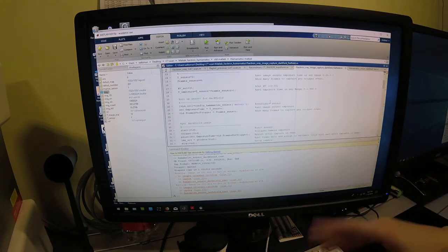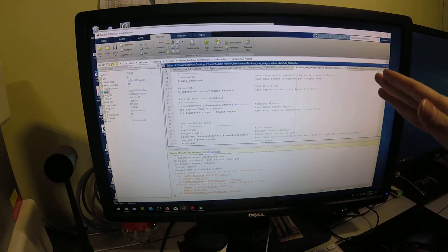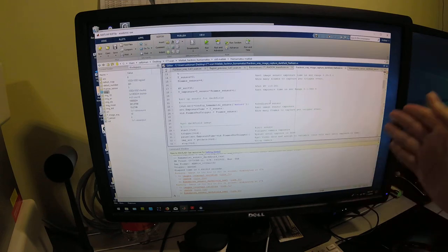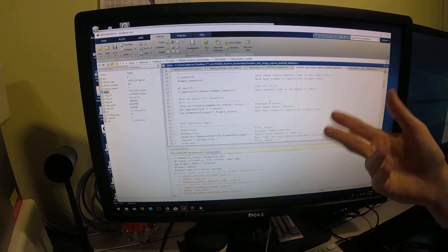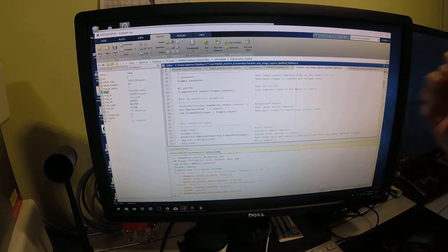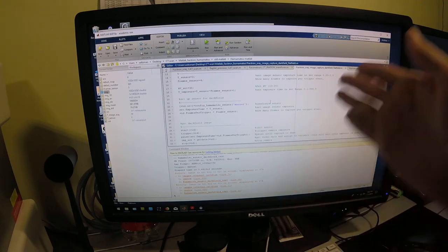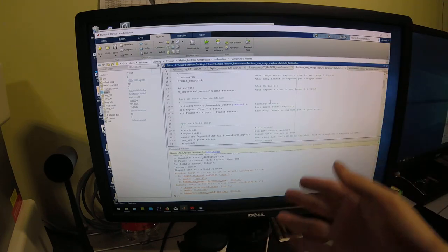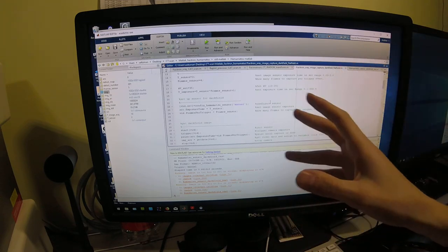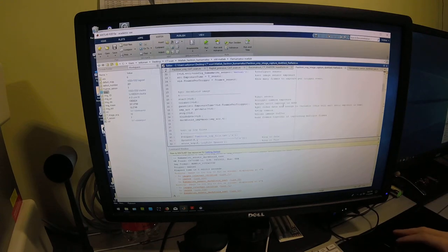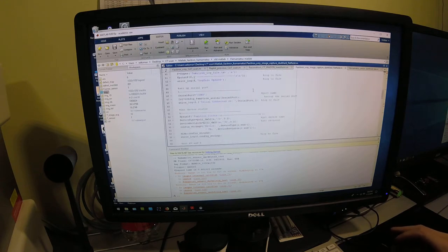In this case, there really isn't any expected heel effect, which would be inhomogeneities due to the angle at which the anode on the X-ray tube intersects the electron beam. The X-ray bremsstrahlung isn't generated just at the surface, but also somewhat inside the anode. So as you get to very acute angles near the cut angle of the anode, you'll start seeing fall-off in intensity. However, we don't actually see that on this system.